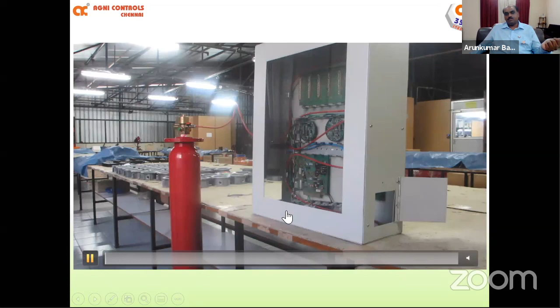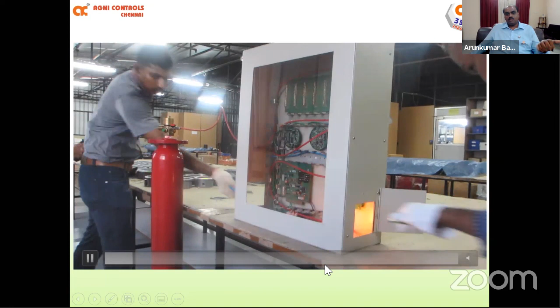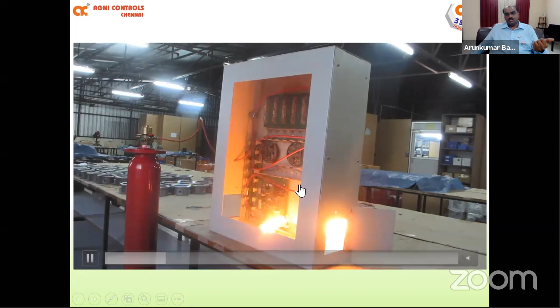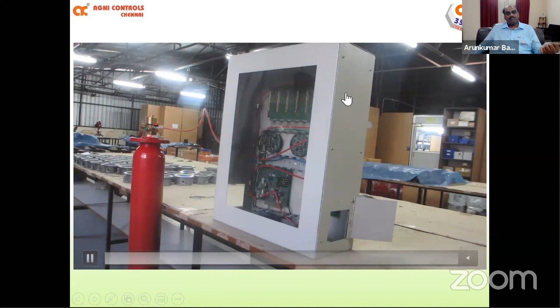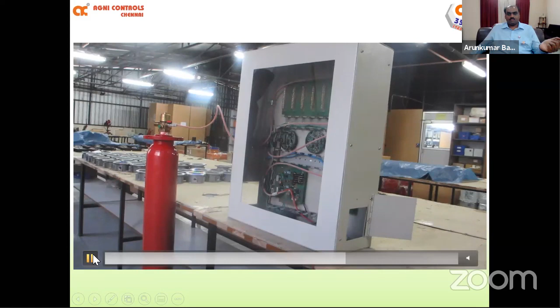For the benefit of viewers, I'm putting the video again. The flame was introduced, and within the next 5 seconds the tube burst and the entire flame was extinguished, and the cabinet now gets into an inert kind of atmosphere so that no reignition occurs inside the panel.